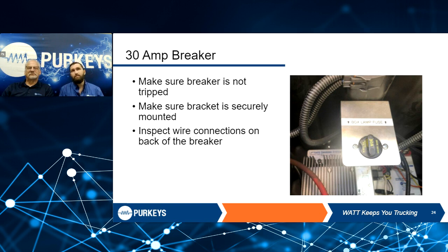As an extra precaution, I like to go through and double check my voltages on it. On the back side you've got two threaded bolts, and that's for both of your output wires. I like to go through with my multimeter and check voltages on both of those studs, just to ensure I'm not seeing any differentiating values on my voltage readings.